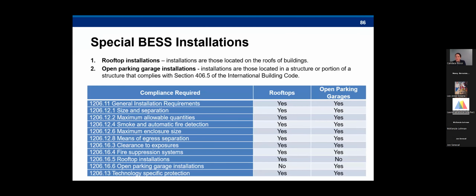So the code also spells out 2 additional locations, which they call special battery energy storage installations. So these are for projects that are installed on rooftops or open parking garages. They have similar requirements to the indoor and outdoor systems, in that they need to meet the general installation requirements, size and separation. They have to meet that, as well as maximum allowable quantities. But they have some additional requirements that are specific to rooftops and open parking garage installations. So we'll talk through those.